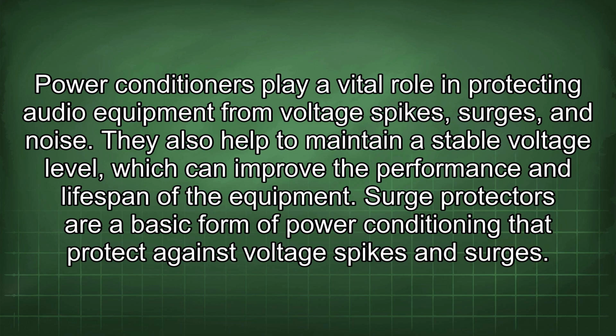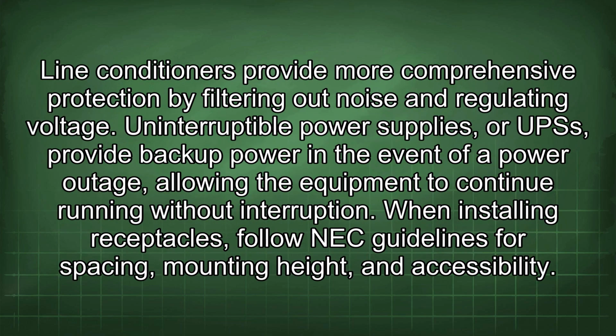Surge protectors are a basic form of power conditioning that protect against voltage spikes and surges. Line conditioners provide more comprehensive protection by filtering out noise and regulating voltage. Uninterruptible power supplies, or UPSs, provide backup power in the event of a power outage, allowing the equipment to continue running without interruption.